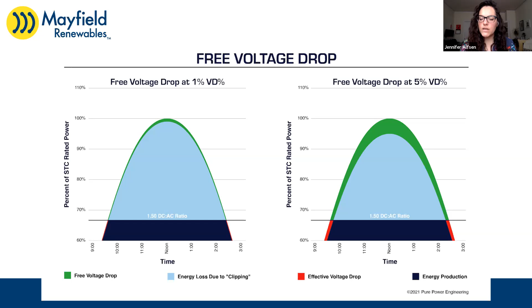Let's keep going—do we have another slide beyond this, or is this the last one for the voltage drop topic? We have one more. So what are we looking at here? This is showing the different DC to AC ratios, whereas the previous one showed different voltage drop levels. This assumes the same voltage drop percentage, comparing a 1.5 versus a 1.2 DC to AC ratio.